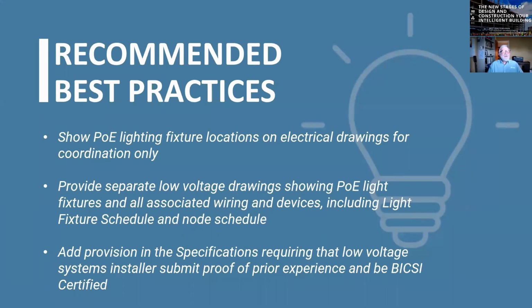Show the PoE lighting fixtures on the electrical drawings for coordination, but don't show all the low voltage details on the electrical drawings. Typically, you're going to have electrical drawings that show the power plans, receptacles, equipment that needs to be powered. You're going to have drawings that show the light fixtures, the switches, and those kinds of things. Then you're going to have maybe a set of sheets that show riser diagrams, one line diagrams, then maybe details, schedules, and those kinds of things.